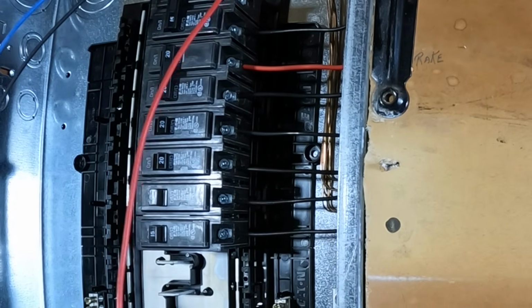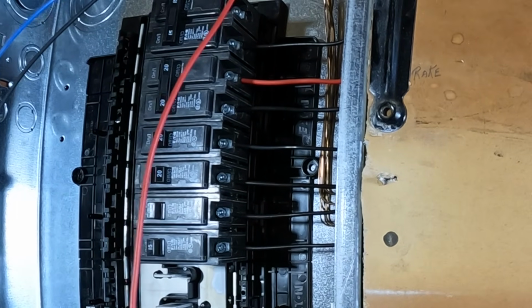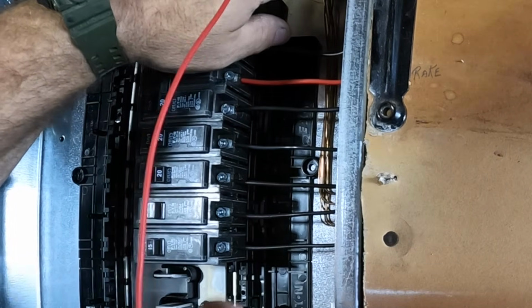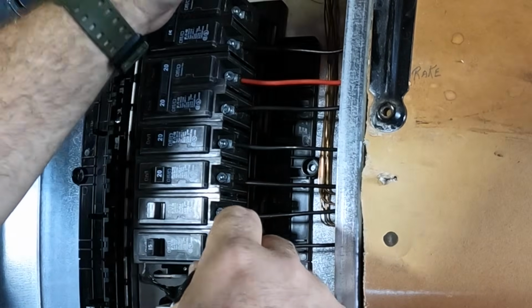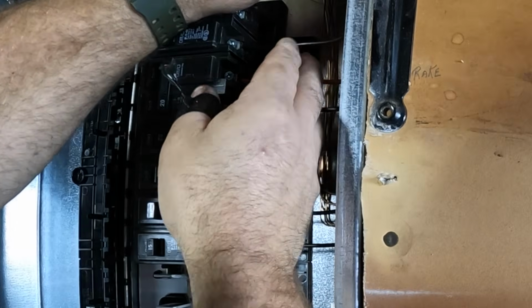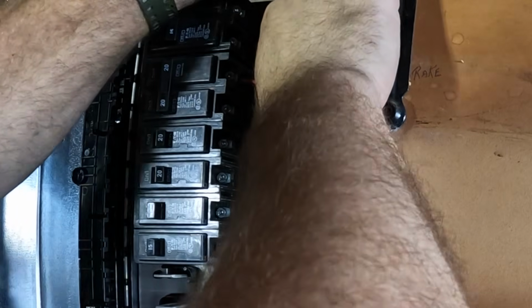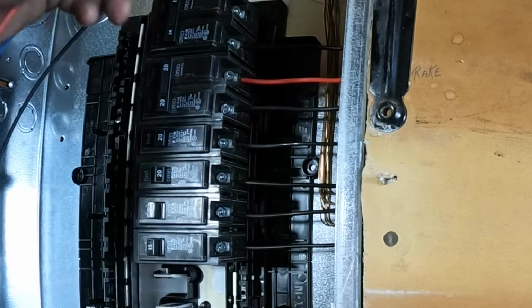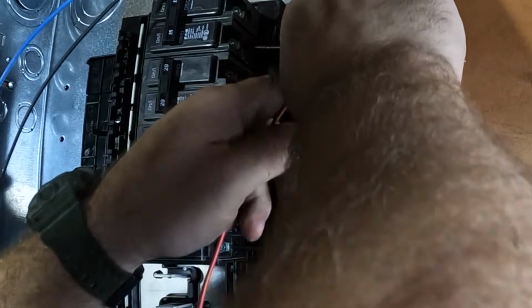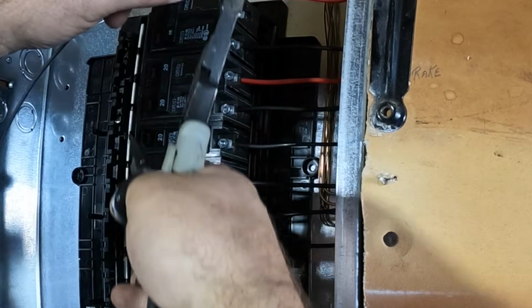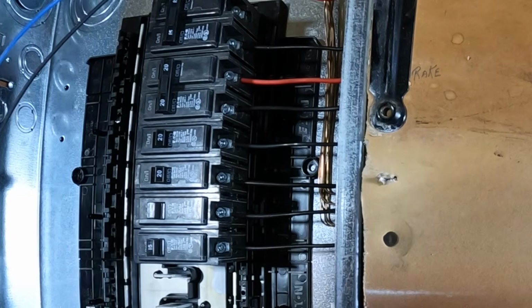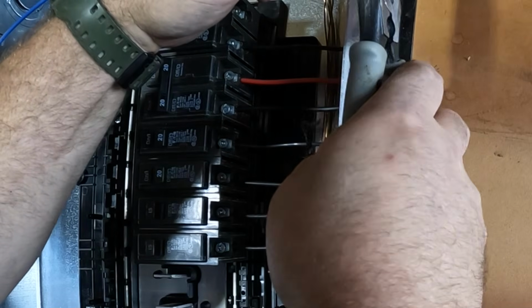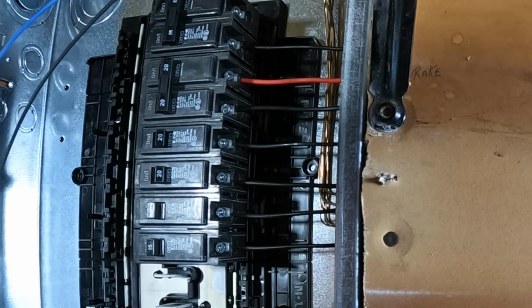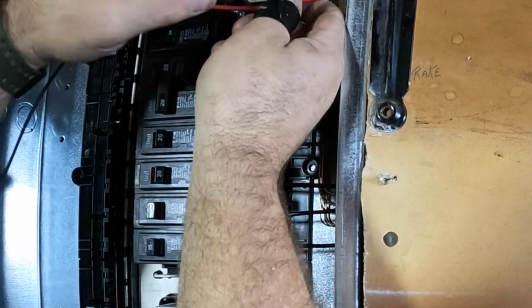If you were to turn off just one of those circuits, you would still have current flowing through your neutral conductor. And so the code changed a few years ago to require that both of the branch circuits on a multi-wire branch circuit be disconnected or turned off at the same time, so you cannot get on that neutral and possibly get shocked by it. So that's the purpose of the common trip double pole circuit breakers for all multi-wire branch circuit conductors.